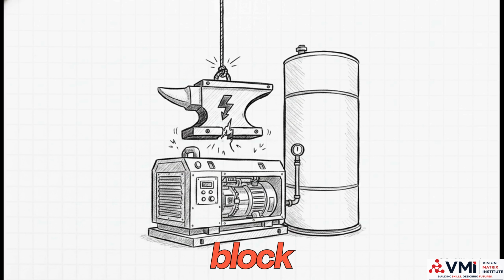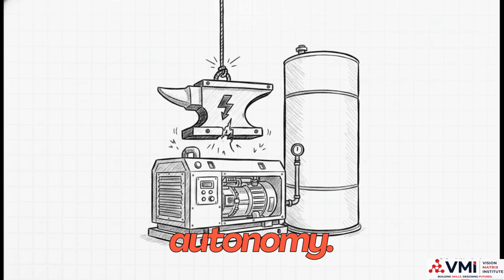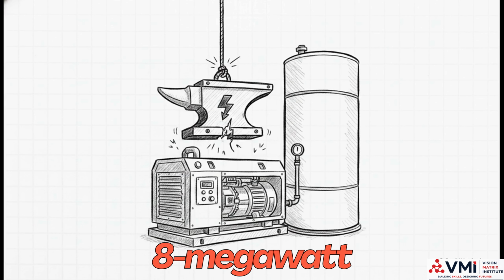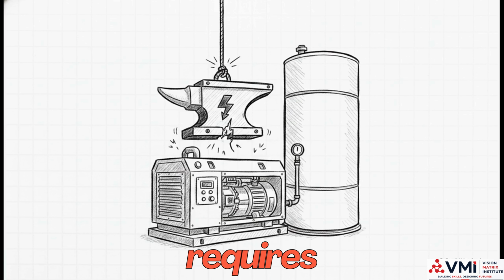Engineers have to account for block loading. Imagine dropping a massive physical weight onto a spinning engine. You have to know exactly how much electrical weight the generator can take all at once without stalling. They even have to calculate fuel autonomy. Keeping an 8-megawatt facility running for just 8 hours requires over 16 cubic meters of diesel fuel.